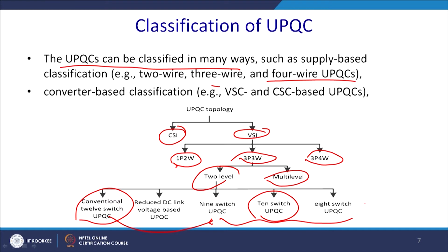The conventional 12 switch topology is for the 2 level. We shall see these topologies, and thereafter, instead of the 12 switch, we can have a 9 switch topology. There are combinations where some switches are shared between series and shunt. So, that is the reported topology, and the 10 switch topology is also the same thing. These are the reduced switch topologies, where ultimately it shares the part of the current and voltage. So, one leg or something is common for both, so that it reduces the number of switches.